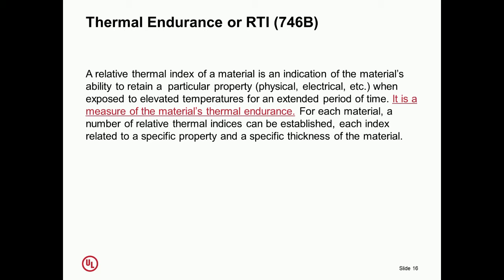If we look at thermal endurance, we're trying to say how well can that material maintain the properties it has now over time when it's stressed thermally. It's not a predictive model. It's not saying a material will last a given amount of time. It's not trying to assess the lifetime of an end product. It's clearly a bar of entry for the use of the material in an electrical product where it provides both physical and electrical benefits.